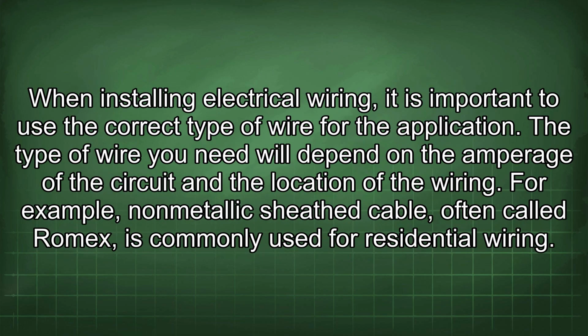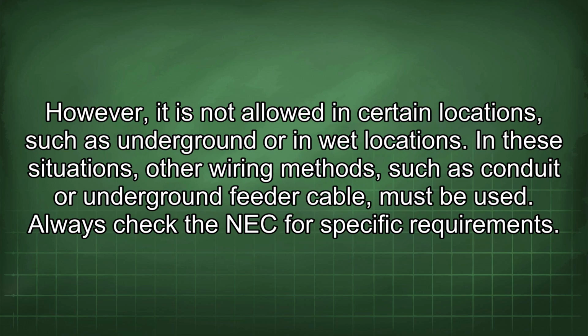When installing electrical wiring, it is important to use the correct type of wire for the application. The type of wire you need will depend on the amperage of the circuit and the location of the wiring. For example, non-metallic sheath cable, often called Romex, is commonly used for residential wiring. However, it is not allowed in certain locations, such as underground or in wet locations. In these situations, other wiring methods, such as conduit or underground feeder cable, must be used. Always check the NEC for specific requirements.